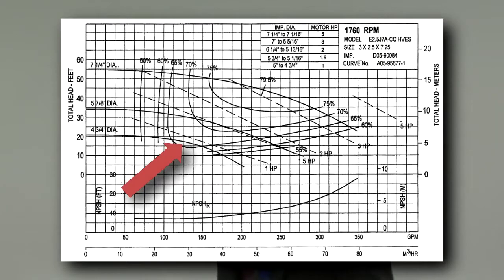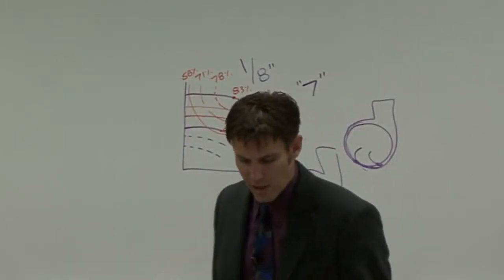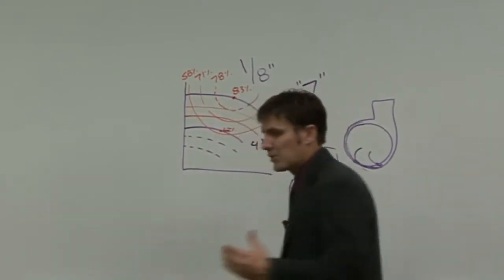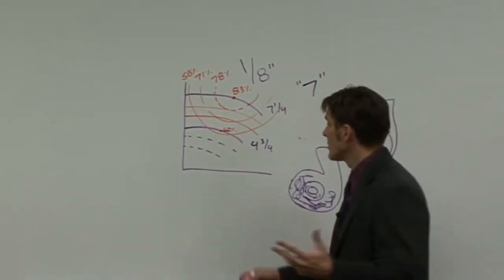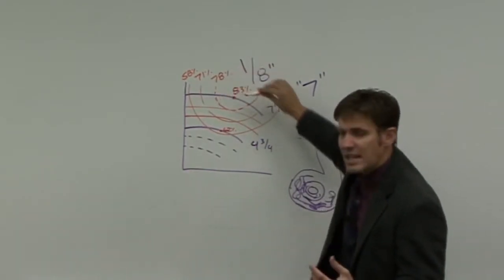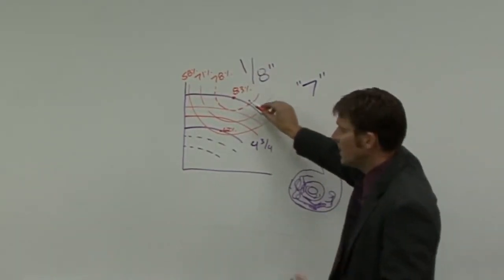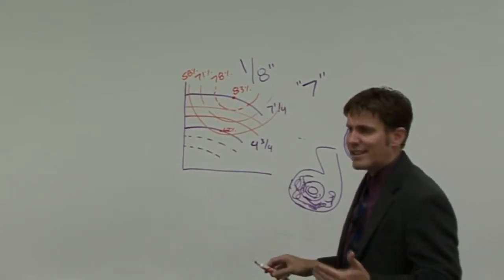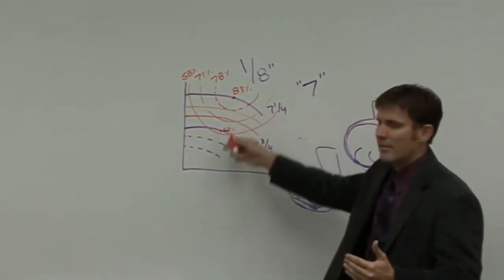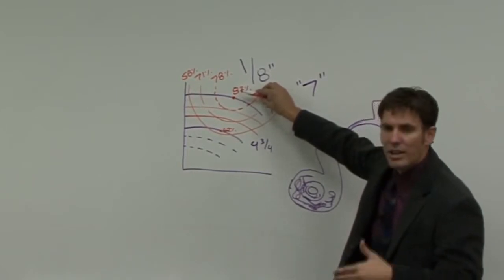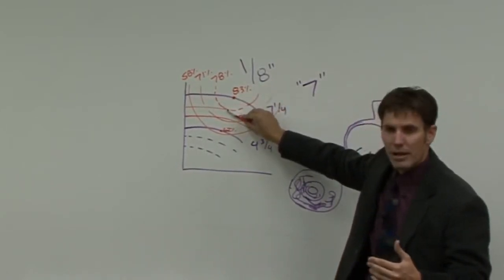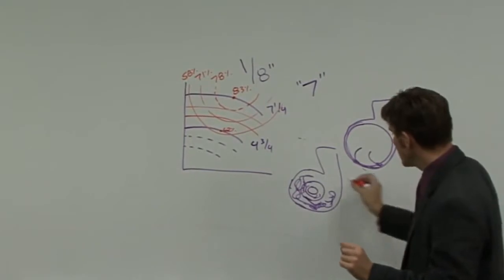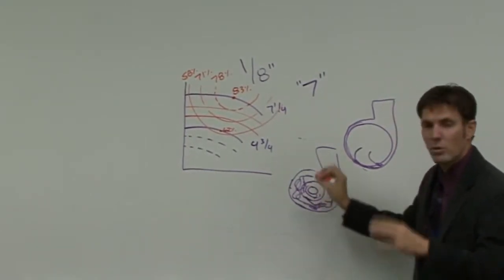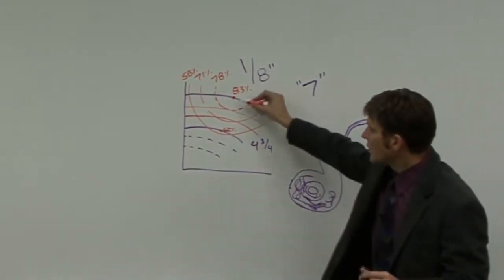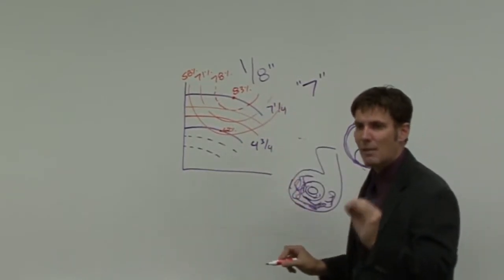So there's not much that we can do if we're going to trim that down, because we've just opened up that space way too much. Now, we're going to talk about this when we get into part 2 of the webinar series. But when we use VFDs, a VFD, as it slows that pump down, it's just like trimming that impeller. If I slow that pump down in speed, I'm rotating on a different impeller line. The difference is I didn't shave all that metal off, so I don't have water just doing what it wants to out here. So it's like trimming my impeller, but keeping the same efficiency.